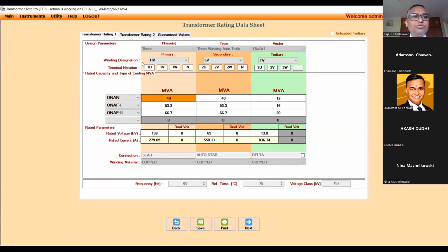Okay, we are now on transformer rating 1. It talks about the 3-phase, 3-winding auto transformer having vector group YNa0d1. Okay, the winding designations you can see here. It is all settable by the user the way he wants it. It could be HV for the primary, HT or AT, whatever it is. Similarly, for the secondary winding, he can choose whatever he wishes to. Similarly, for the tertiary winding. The terminal notations can be different throughout the globe, and that's what this facility is for, to key in whatever one chooses.